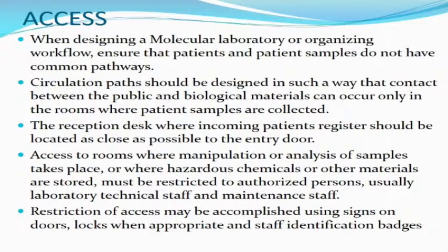Reception desks where incoming patients register should be located as close as possible to the entrance door. The patient shouldn't go into the molecular laboratory setting, because it is risky, for sample collection. Access to rooms where manipulation or analysis of samples takes place, or where hazardous chemicals or other materials are stored, must be restricted to authorized personnel, usually laboratory technical staff and maintenance staff. There should be restriction, and there should be signages on the door or on the equipment about safety requirements or procedures.